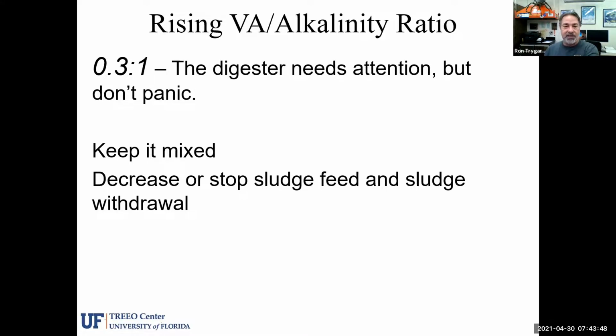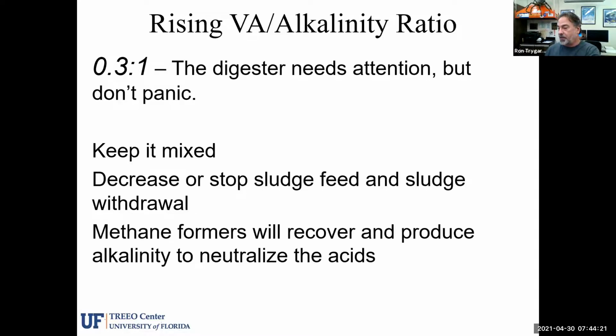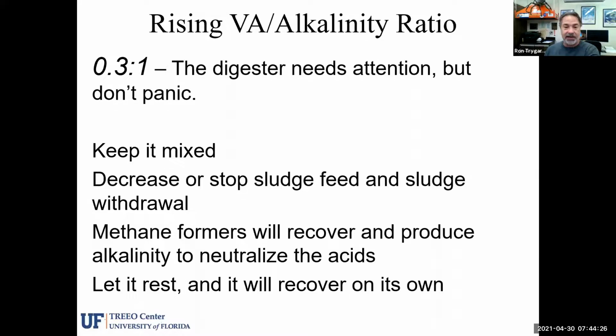Just leave it kind of rest, just like when you don't feel good and you want to take a day off and just lay in bed and get over the flu or a cold. Think about it like this: it wants to just rest. Don't try to keep feeding it, and it will recover, because the bacteria, the methane formers, will consume the volatile acids and they will produce alkalinity. So this number will come back on its own once the methane formers can keep up with the acid that's being formed. So let it rest, let it recover on its own.